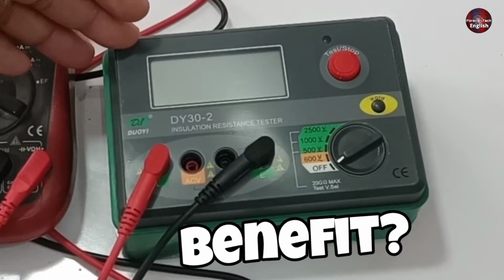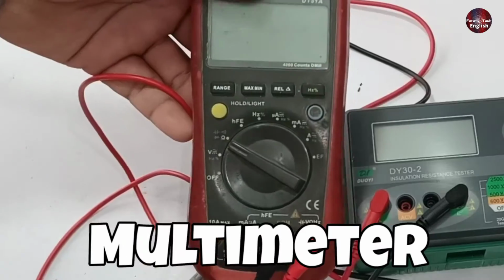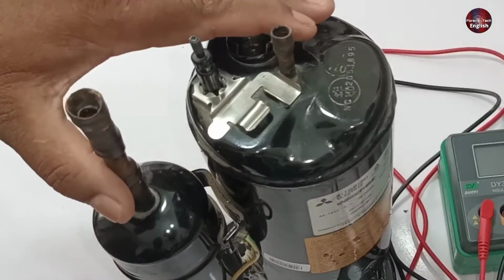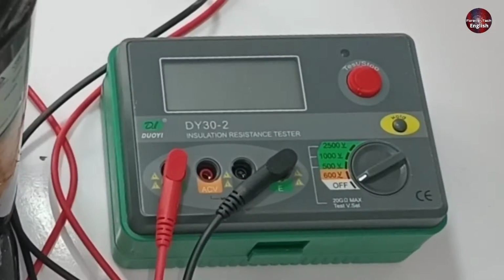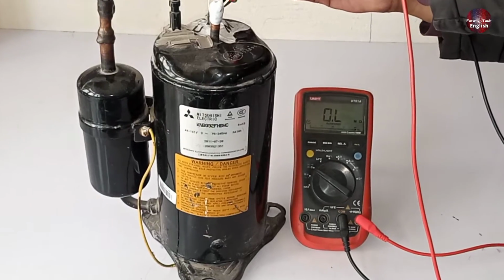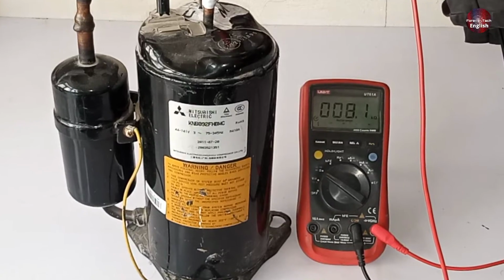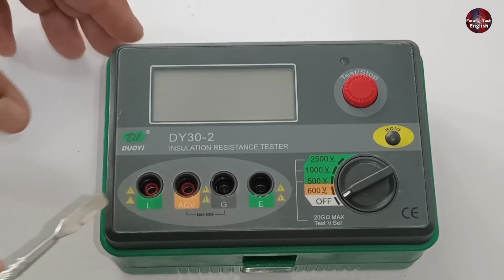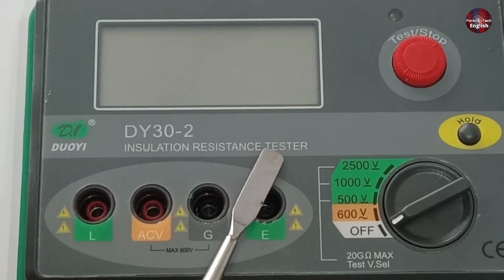What is the benefit of an insulation resistance tester over a multimeter? I will test the compressor and different things with this megger. The compressor can also be tested with a multimeter, but why is a megger preferable? So, friends, a megger is an insulation resistance tester.